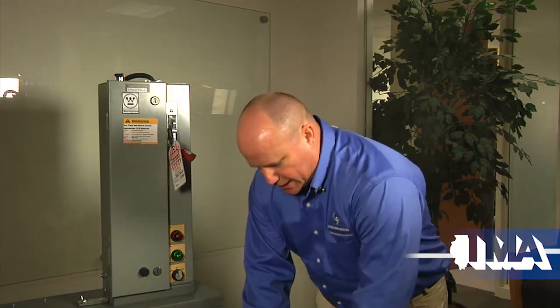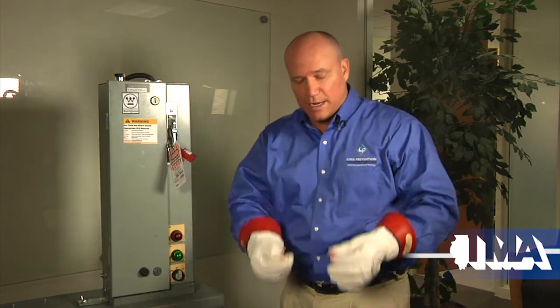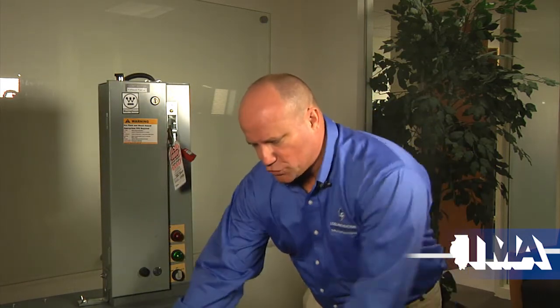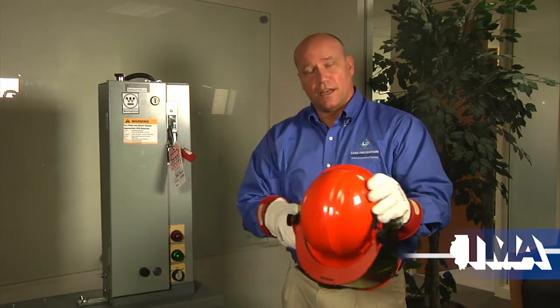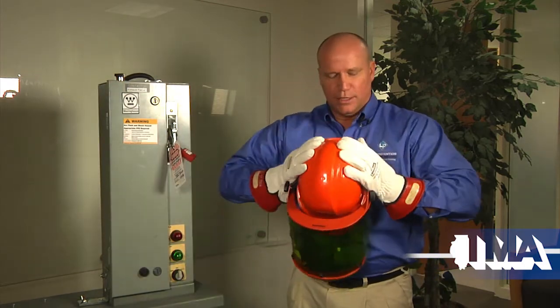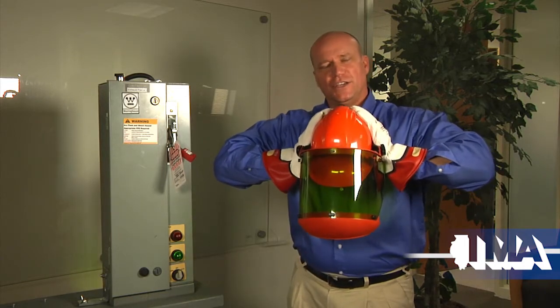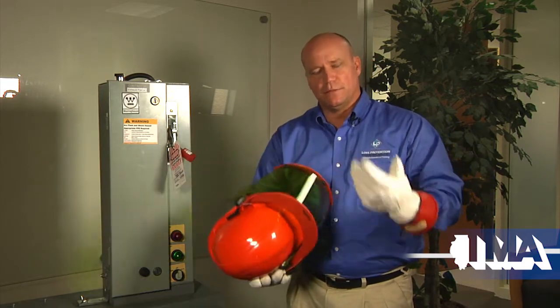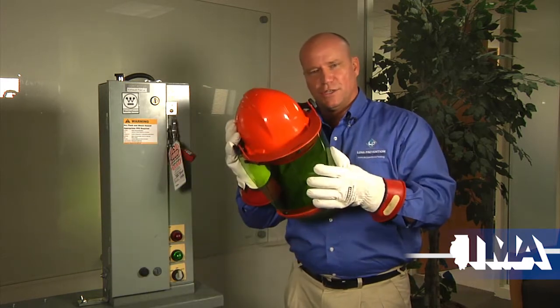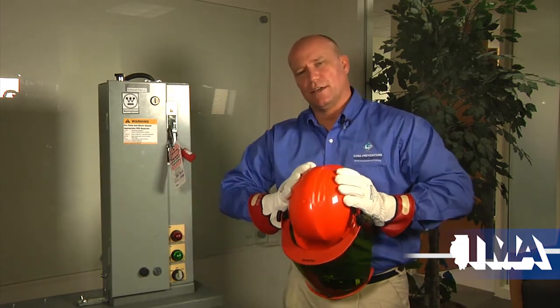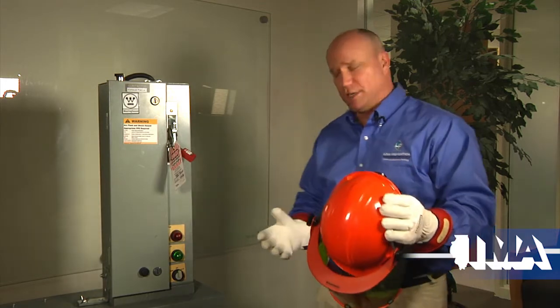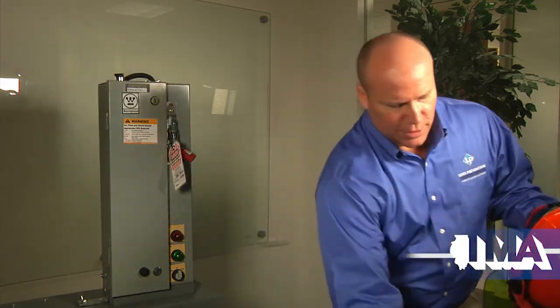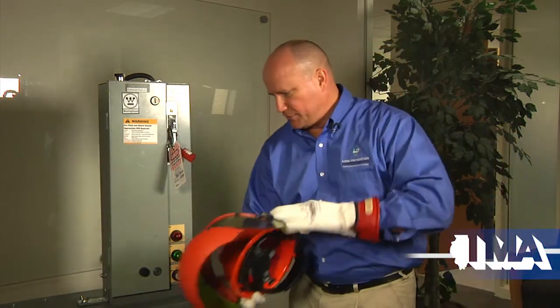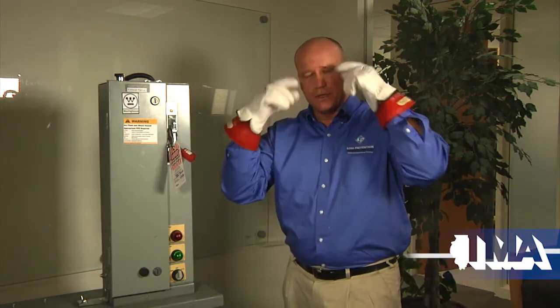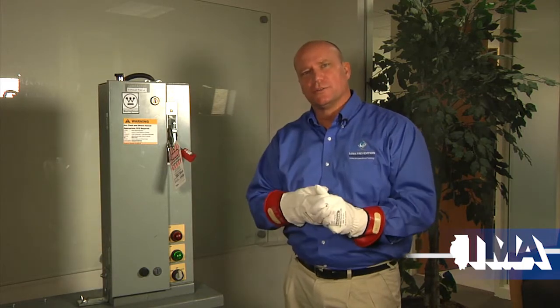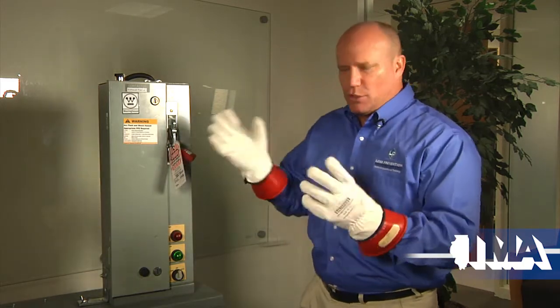Okay. The next thing I would have to wear is hearing protection, which I'm not going to put on, just for training purposes, just so I can show you that obviously you need it. I also need to have my face shield, and this is, like I said, the minimum for this particular scenario. The face shield's intact. I do a quick compression test on my helmet. This helmet is either a Class E or Class G helmet. And then the last thing is a pair of safety glasses or safety goggles over the top, underneath, so that you protect your eyes from shrapnel damage. Okay, so those are some of the things that you would have to have on.